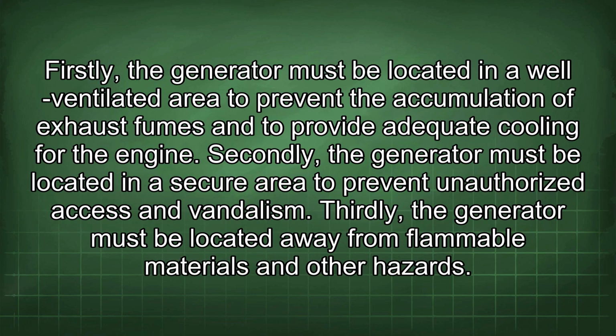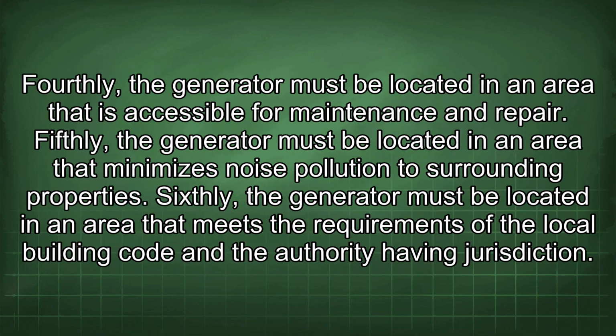Firstly, the generator must be located in a well-ventilated area to prevent the accumulation of exhaust fumes and to provide adequate cooling for the engine. Secondly, the generator must be located in a secure area to prevent unauthorized access and vandalism. Thirdly, the generator must be located away from flammable materials and other hazards. Fourthly, the generator must be located in an area that is accessible for maintenance and repair. Fifthly, the generator must be located in an area that minimizes noise pollution to surrounding properties.